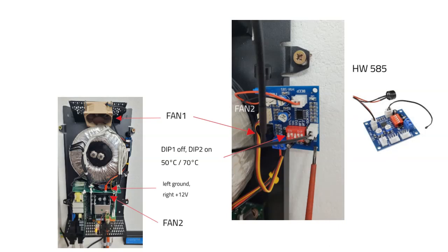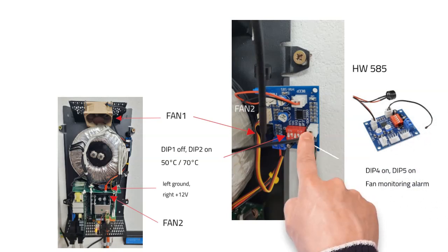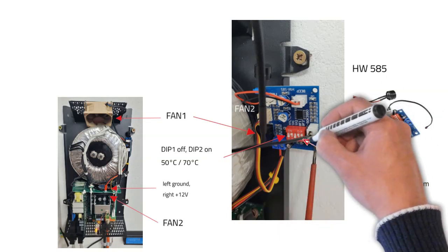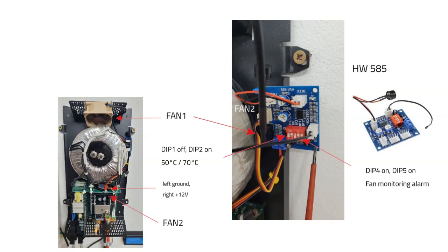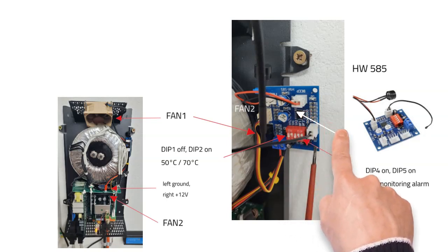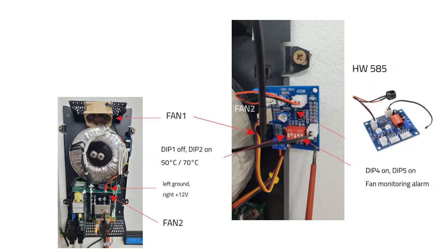Dip switches 1 and 2 are set to off and on so that the upper fan starts at 50 degrees Celsius and reaches its maximum speed at 70 degrees Celsius. Dip switches 4 and 5 are turned on so that an alarm occurs if a fan does not rotate. The speed of the lower fan can be set to maximum speed using the associated fan 2 potentiometer.